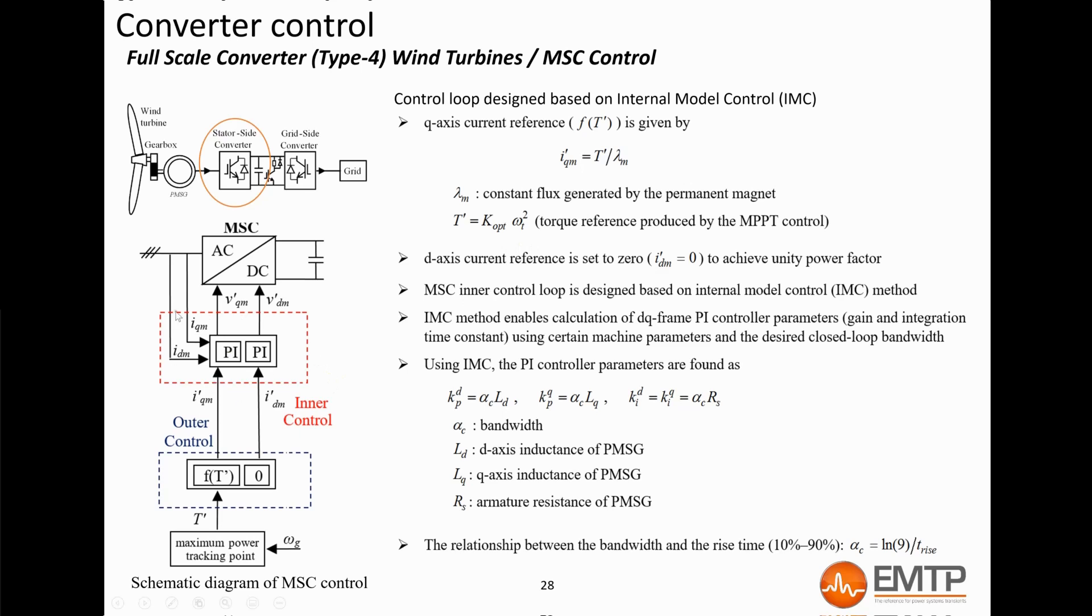The inner loops control the converter voltage to follow the references of the outer loops. The gains, which are the same for D and Q-axis, are calculated as shown here. They are using the machine parameters and follow the internal model control method. In the generic model mask, users can set the rise time, which determines the inner loop speed. It is typically set to 20 milliseconds.